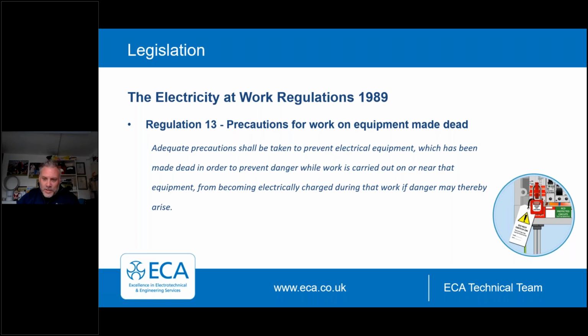Understand that a means of locking off an isolator may be used where such facilities are not available. The removal of fuses or links and being held safe can provide a secure arrangement if proper control procedures are used. It may be appropriate for safe isolation procedures to be formalised in written instructions, including company policies and procedures - that's often a really good procedure.